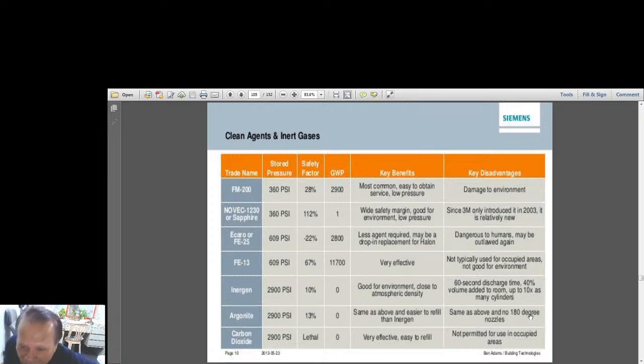Same as above, and no 180-degree nozzles. Oh my God! So same as, because Inergen is also argonite. Carbon dioxide. This is 2,900 psi. It is lethal because it totally displaces oxygen. Very effective, easy to refill. Not permitted to use in occupied areas. So like I said, if you have occupied areas, if you have people working inside the rooms, then you do not like CO2. Okay.